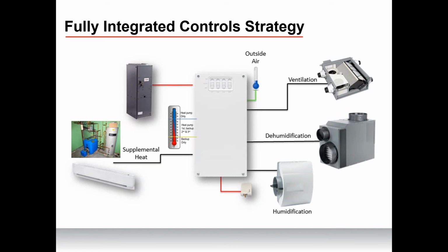This is a fully integrated control strategy. So you think, okay, how do I do all of these things? How can I do it and operate everything in this house from one platform, from one standpoint? There's numerous methods available to tie in multiple pieces of equipment to one control's front end. So think of home and building management systems such as BACnet, Modbus, Savant, etc. You can tie those in, they work utilizing our third-party thermostat interface and third-party controls. A home's entire HVAC system can be managed via a single platform like a BACnet, Modbus, things of that sort. So we can do that with that third-party thermostat interface.